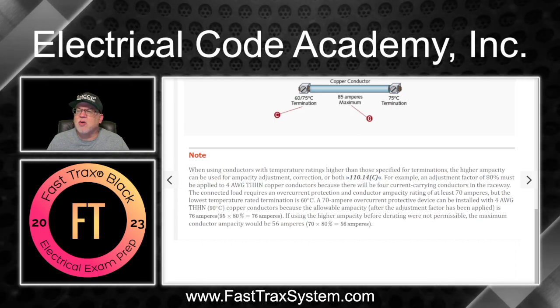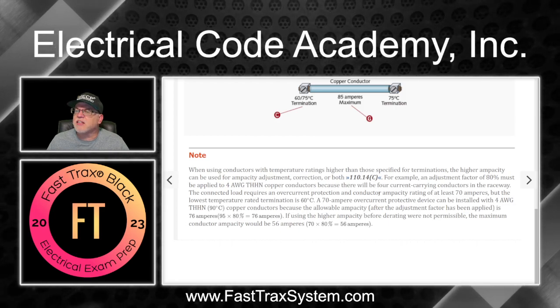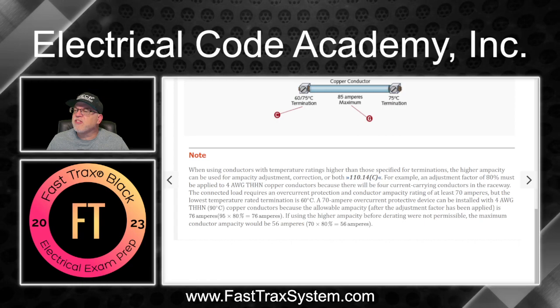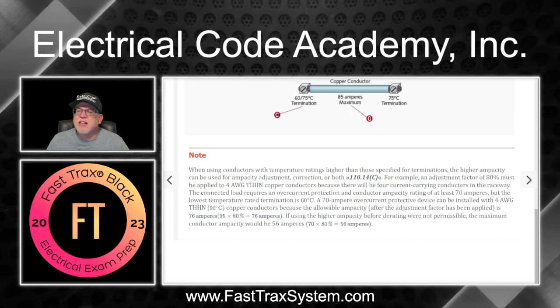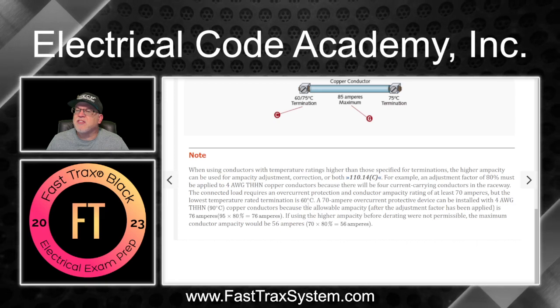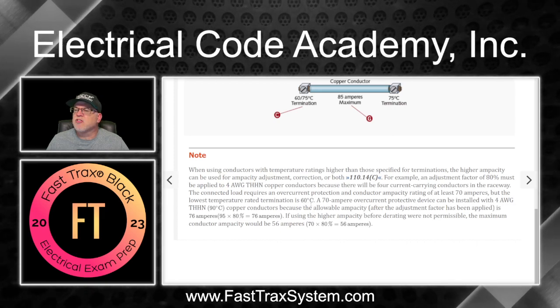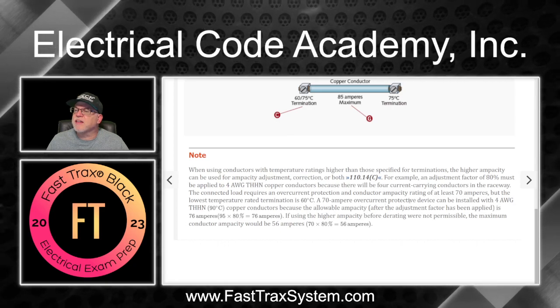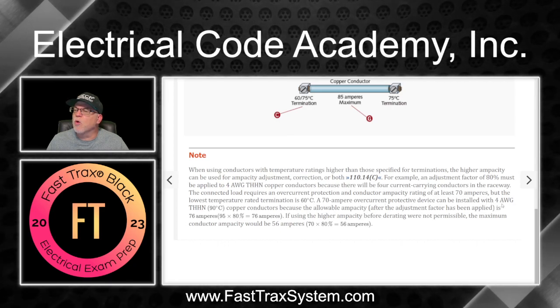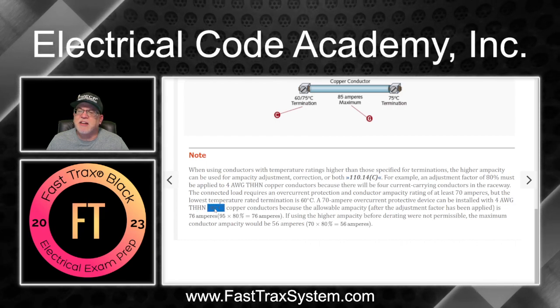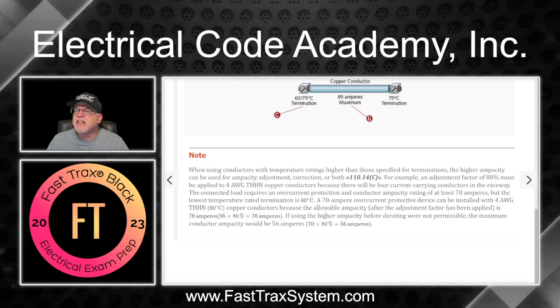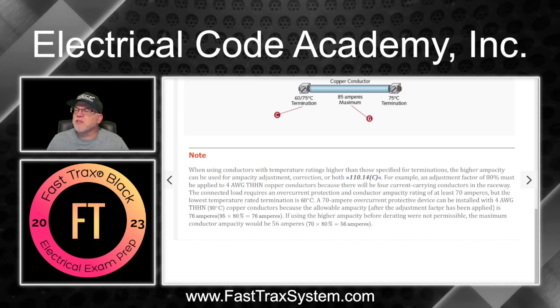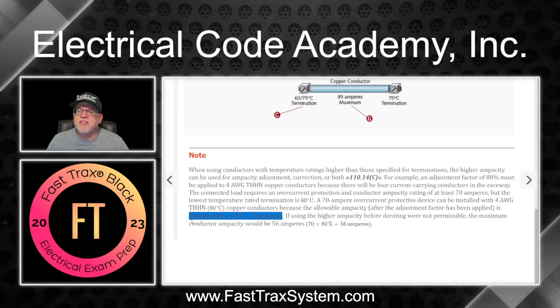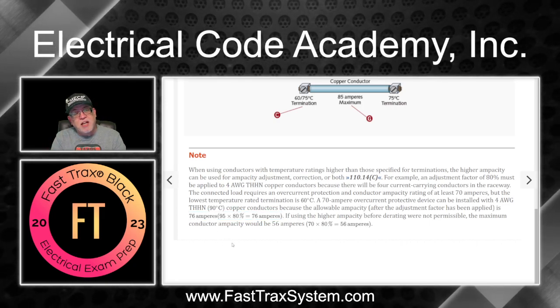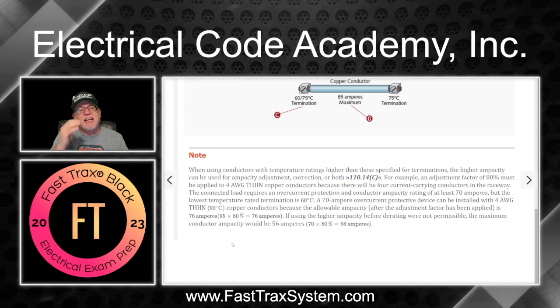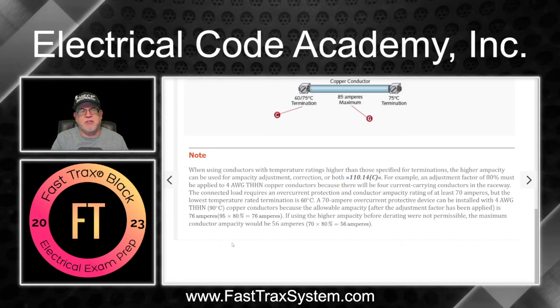So the connected load requires an overcurrent protection and conductor ampacity rating of at least 70 amperes. But the lowest temperature rated terminal is 60 degrees C. Okay? So it says a 70 ampere overcurrent protected device can be installed with 4 AWG THHN 90 degrees C copper conductors because the allowable ampacity after the adjustment factor has been applied is 76 amps. Now why? Because we're able to use the insulation rating of the conductor for those adjustments or corrections.